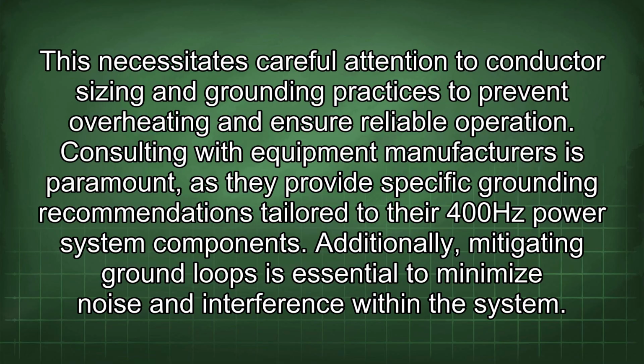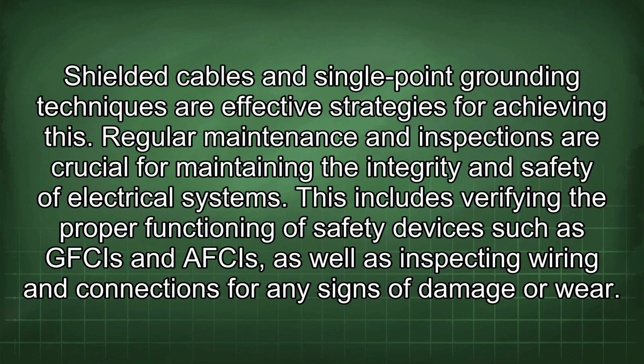Consulting with equipment manufacturers is paramount, as they provide specific grounding recommendations tailored to their 400 Hz power system components. Additionally, mitigating ground loops is essential to minimize noise and interference within the system. Shielded cables and single-point grounding techniques are effective strategies for achieving this. Regular maintenance and inspections are crucial for maintaining the integrity and safety of electrical systems. This includes verifying the proper functioning of safety devices such as GFCIs and AFCIs, as well as inspecting wiring and connections for any signs of damage or wear.